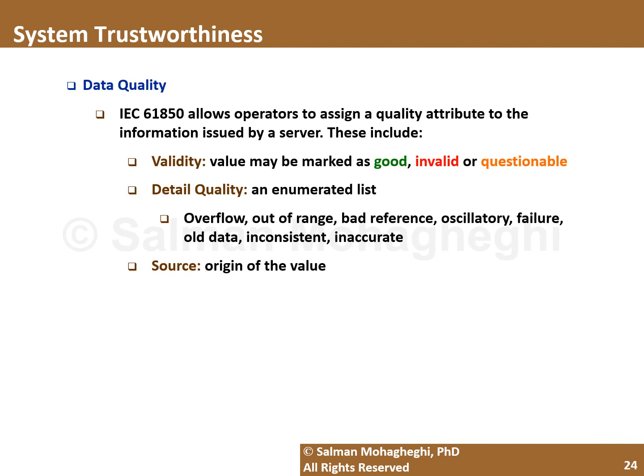Similar to that, we have data quality. That's again another logical node within IEC 61850. This attribute indicates the quality of the data or services provided by that component, and it has some categories. One is validity, which tells you, for example, whether the data being provided to me by a potential transformer or a current transformer is good, invalid, or questionable. And if it's invalid or questionable, then you can detail what the issues are through an enumerated list.